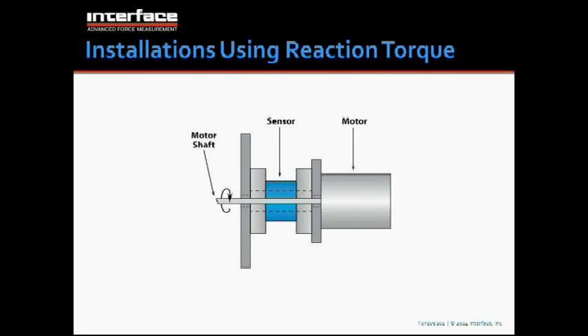Now, when we talk to a customer, typically we want to try and key in on the method of measurement that works best for his application, but also is lowest cost and easiest to implement. A reaction sensor, in many cases, can be a better way to go than using a rotary sensor. They're less expensive, they're less complicated, less to go wrong, and so it should be at least considered in most installations to understand if a reaction sensor could be used. This is an example where a hollow reaction sensor is bolted between a plate and a motor, and then the motor shaft passes through the sensor and then spins.